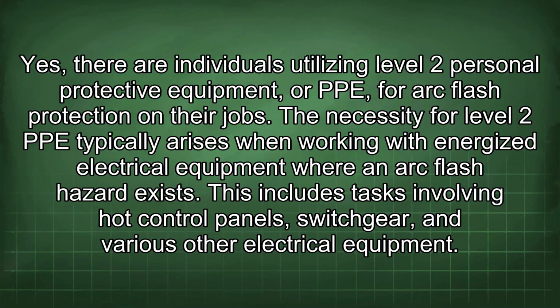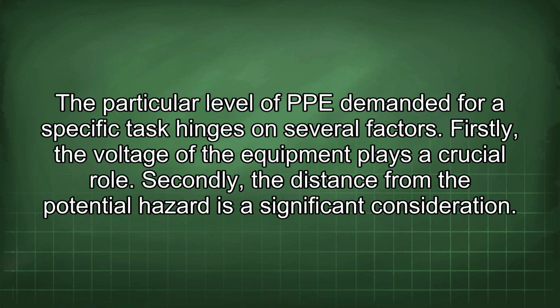Yes, there are individuals utilizing Level 2 personal protective equipment, or PPE, for arc flash protection on their jobs. The necessity for Level 2 PPE typically arises when working with energized electrical equipment where an arc flash hazard exists. This includes tasks involving hot control panels, switchgear, and various other electrical equipment. The particular level of PPE demanded for a specific task hinges on several factors.